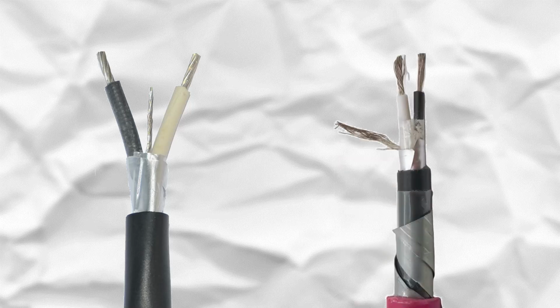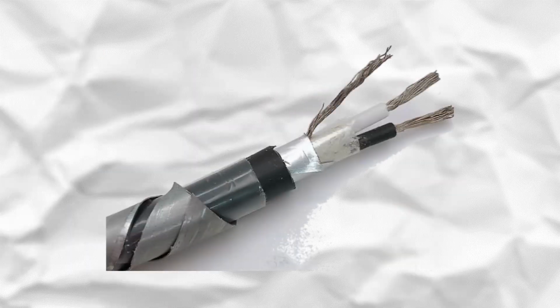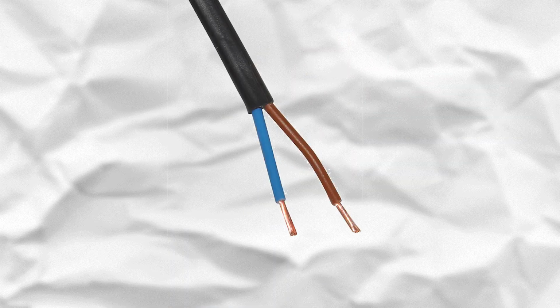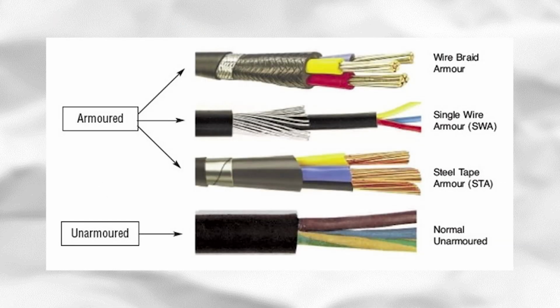For measuring instruments which always send an analog signal to control rooms, a single pair cable is used. In this type of cable, two wires are twisted and there is a bare drain wire alongside it. An aluminum shield covers all the present wires to protect the cable from radio frequency and interference noise. A two-core single cable is used for transferring the status of switches to the control room. The main difference from the pair cable is that these cables do not have drain wire and shield. To protect the cables from mechanical damage, the armor layer might be added on the cable inner sheath. Last but not least, the cable outer sheath is usually made from PVC and it must be halogen-free.